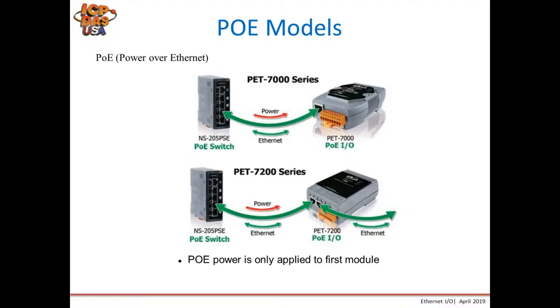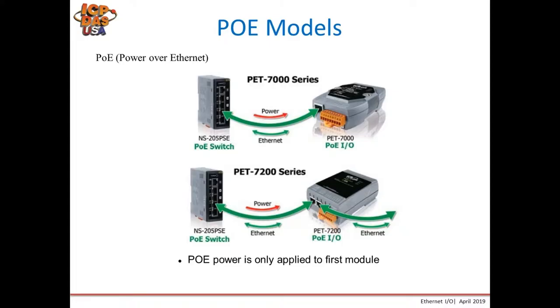This slide shows the Power over Ethernet feature. Note that the part number must include the P — as in PET — to have this feature. With PoE, Ethernet and power are passed through the Category 5 cable so you can power the module without additional power wiring, which is great for large applications to save on wiring costs. For the 7200 series, only the first module receives Power over Ethernet — only Ethernet data is passed through to the second port. So if you daisy chain multiple PET-7200 modules, you will need to separately power the additional devices.